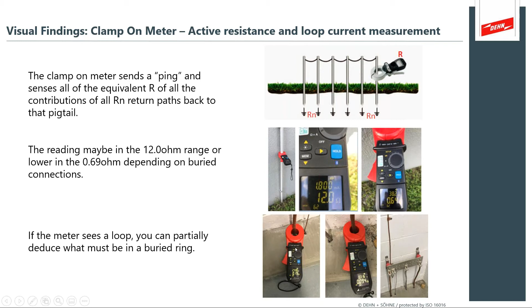If I'm actually measuring earth rods that I know are not connected with a buried connection, then a 12 ohm reading actually is okay. So it's important to know what you're actually looking for. And with this meter, you can inspect and you can detect what you think is there and then deduce what might be part of the buried ring. So it's important to understand that it has limitations, but it's a tool that allows you to deduce what's buried.